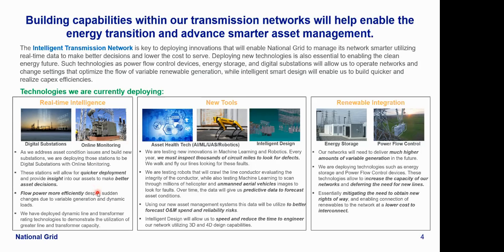We have also deployed technology called dynamic line rating and dynamic transformer rating. This technology enables National Grid to better utilize the existing capacity of its transmission network. I'm going to show you some data later on, but moving from static line ratings and transformer ratings to dynamic ratings is a huge step, which requires a lot of investment, operational changes, and rethinking on how we're going to do system planning if we do have access to this type of data.